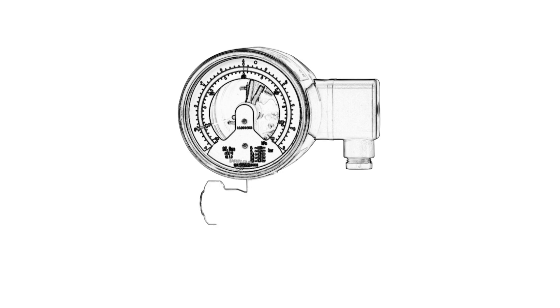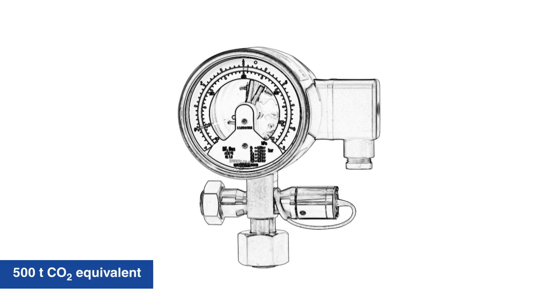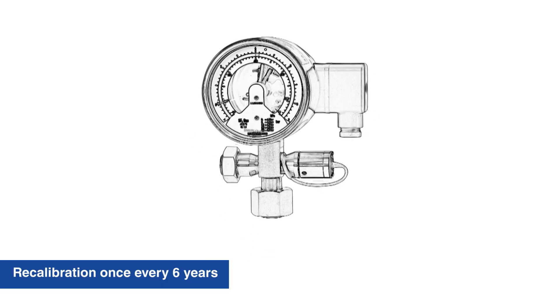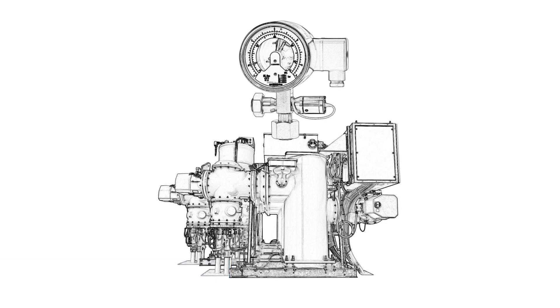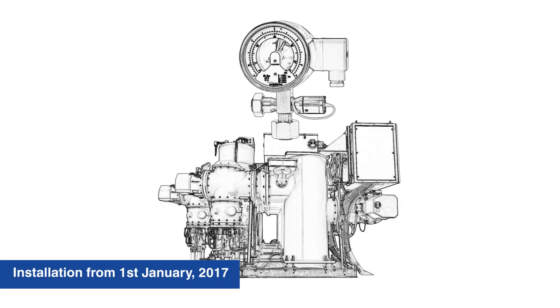Every leak detection system which monitors a gas tank containing fluorinated greenhouse gases in quantities of 500 tons CO2 equivalent or more must be recalibrated at least once every 6 years, as long as the electrical switchgear has been installed from 1st January 2017.